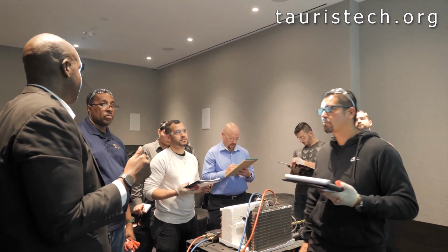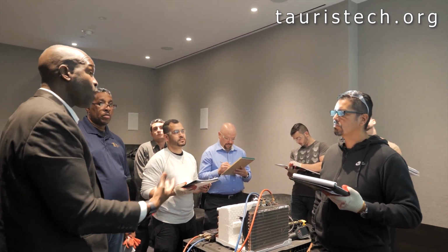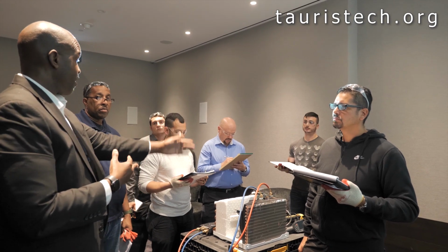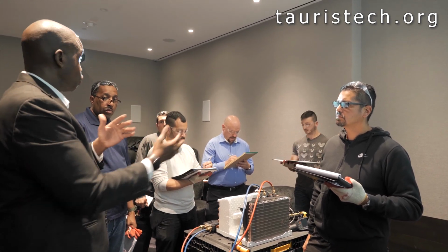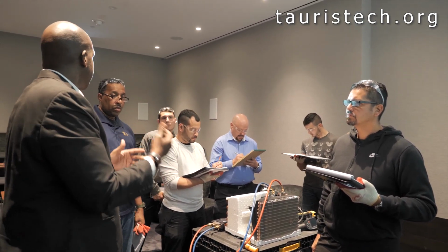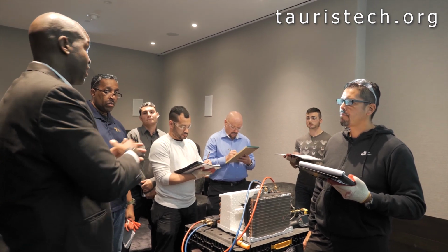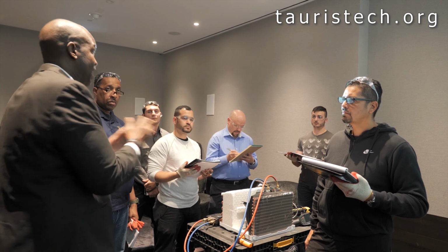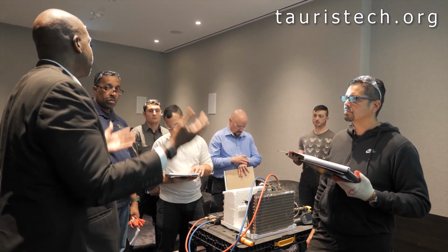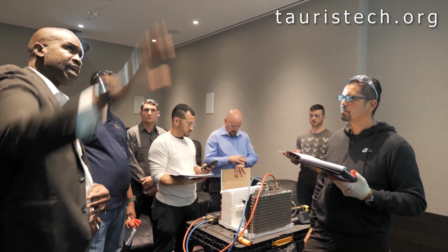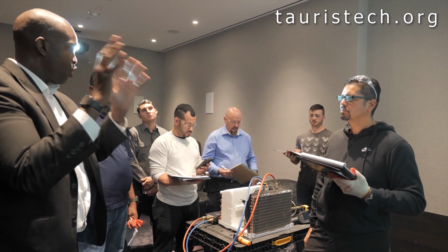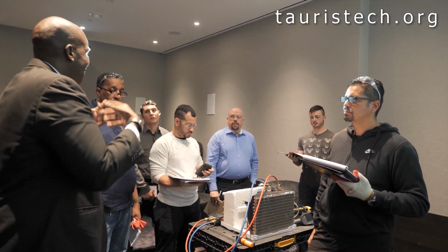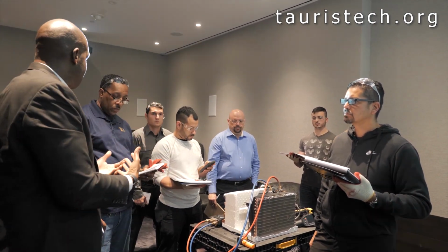Protect the compressor. Right? So that is another way that I'm going to determine if my charge is correct. Usually on most systems, we want about 10 or 15 degrees of superheat. If we got 20, 30 degrees of superheat, then our machine is very undercharged, and we've got to put some more in there. Or we have some kind of restriction. So all of these things, again, are things that we are using to identify what is going on inside of our machine.